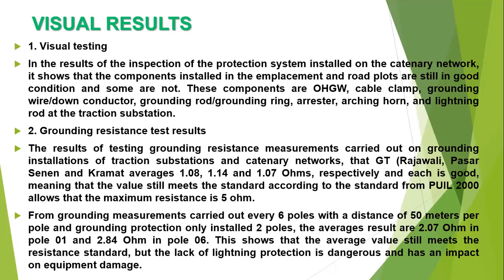Visual result. Number 1, visual testing. The result of inspection of the protection system installed on the catenary network shows that the components installed in the emplacement and road plots are still in good condition. These components are OHGW, cable clamp, grounding wire or down conductor, grounding rod or grounding ring, arrestor, arcing horn, and lightning rod at the traction substation.